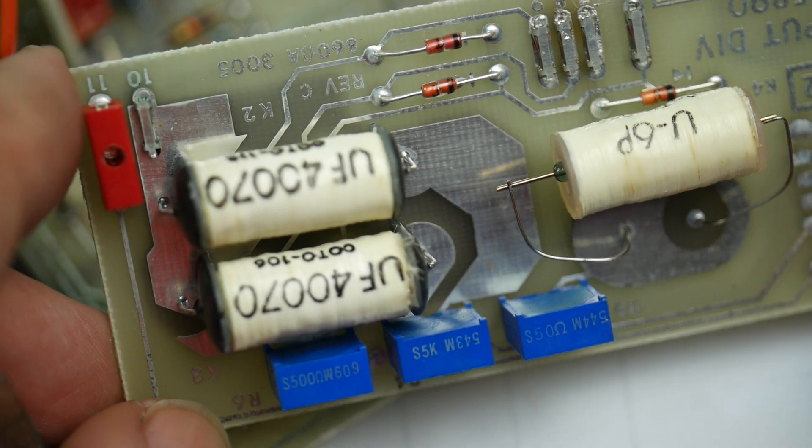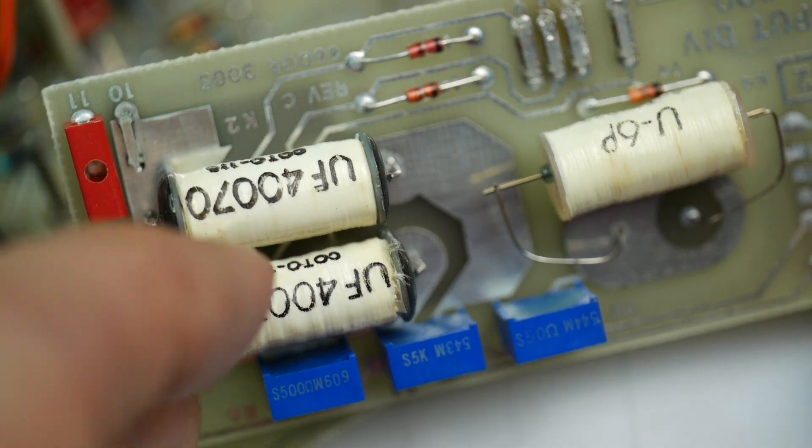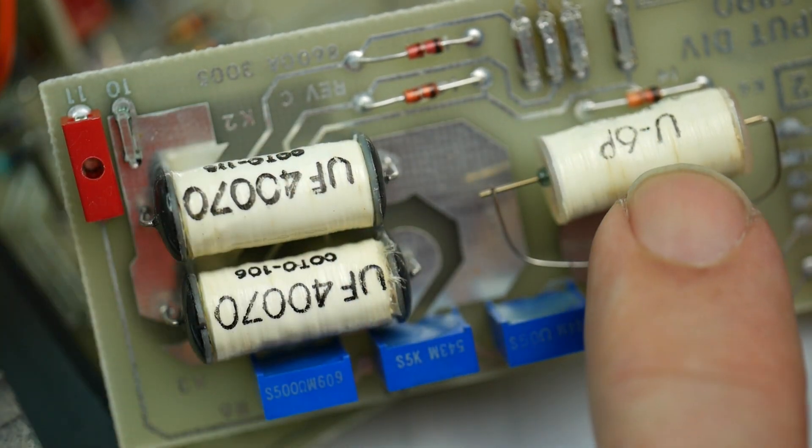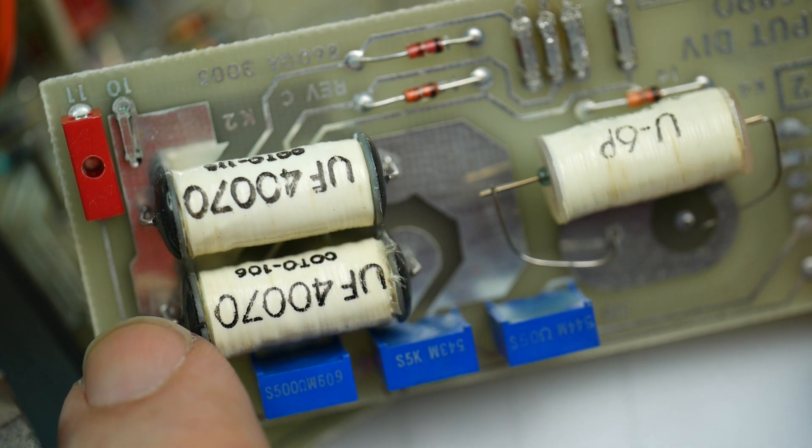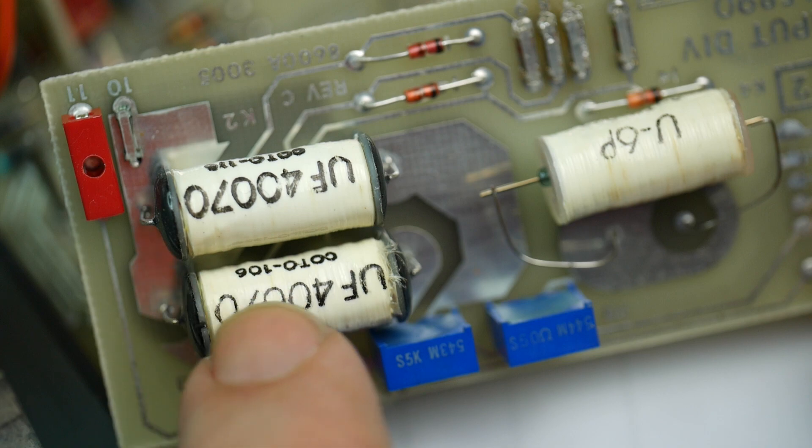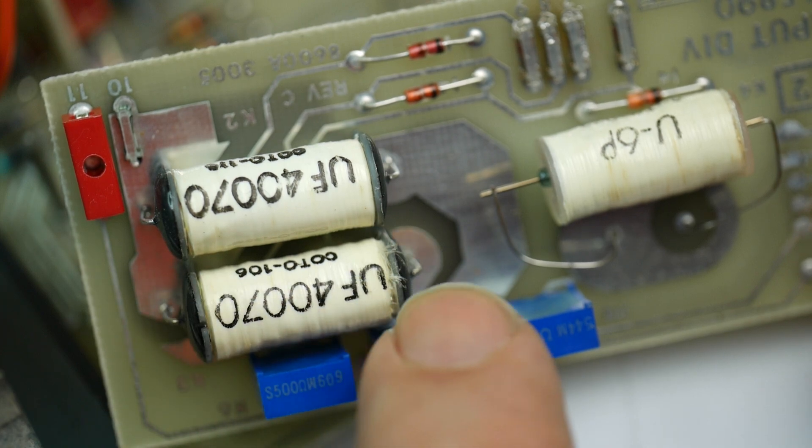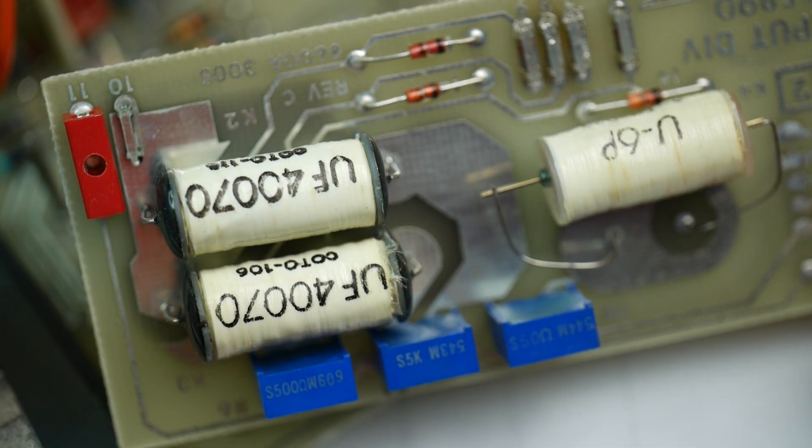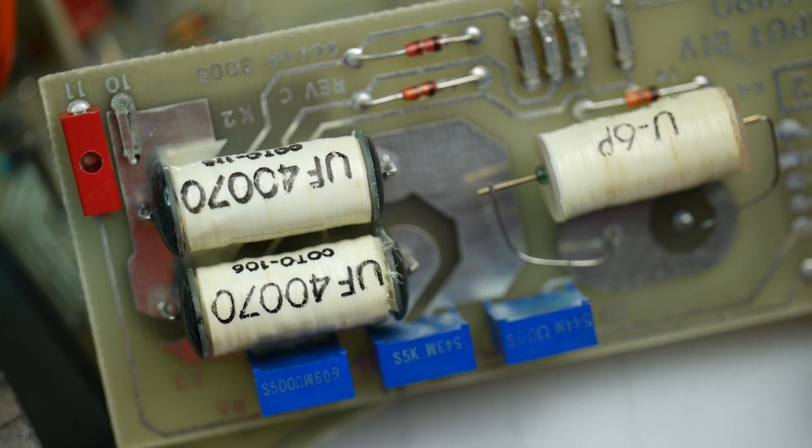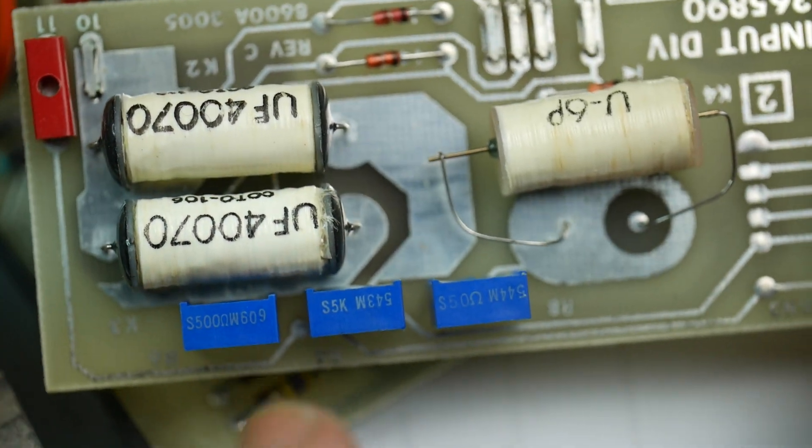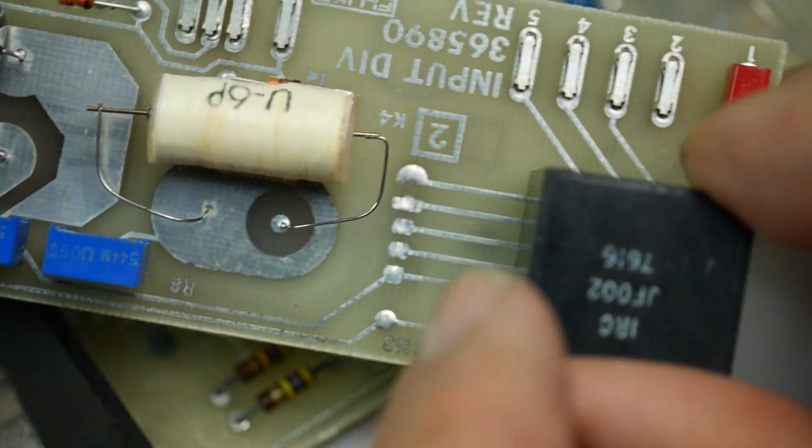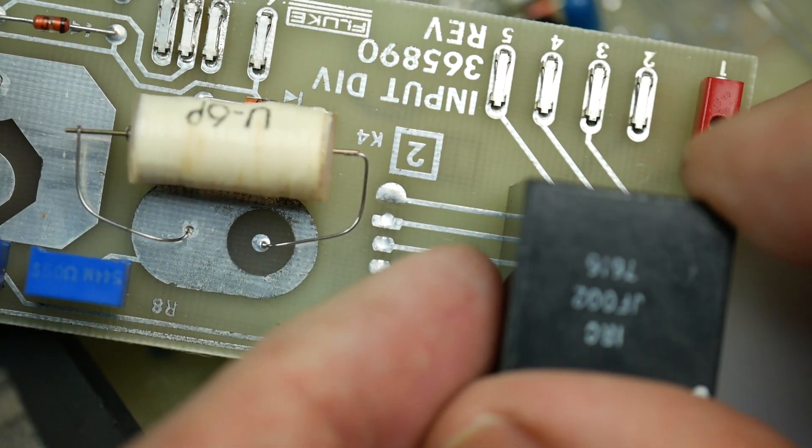So this thing has got reed relays and they will switch on. The reed is down in the middle, there's a coil around it. They switch on when you energize the coil and they close the reed contact. And you can just hear them ting slightly when they do that. And so that's what's selecting the ranges. There's precision resistors in this potted module here.